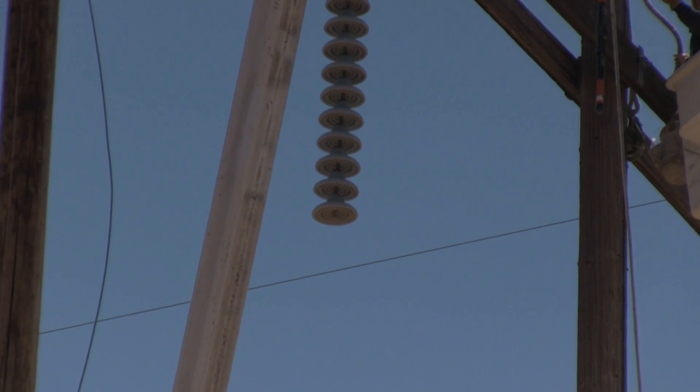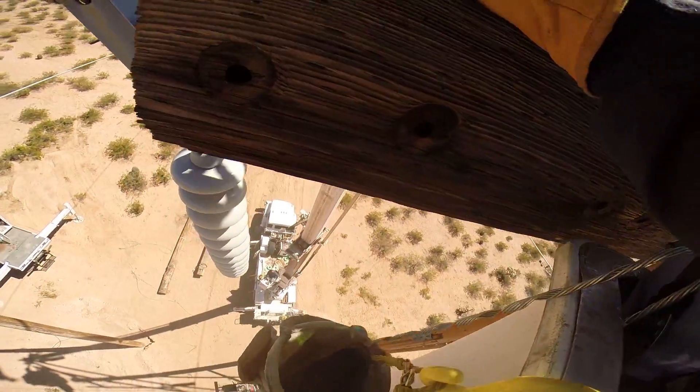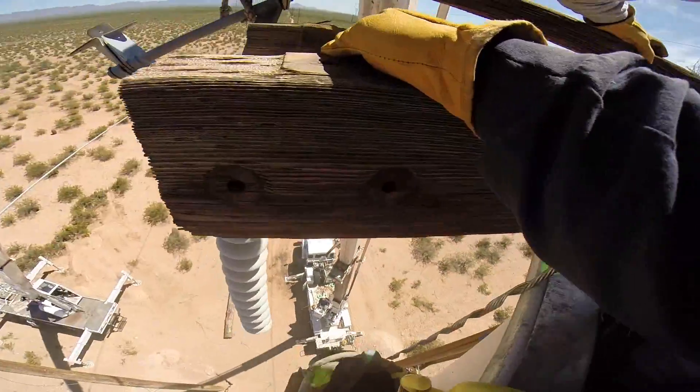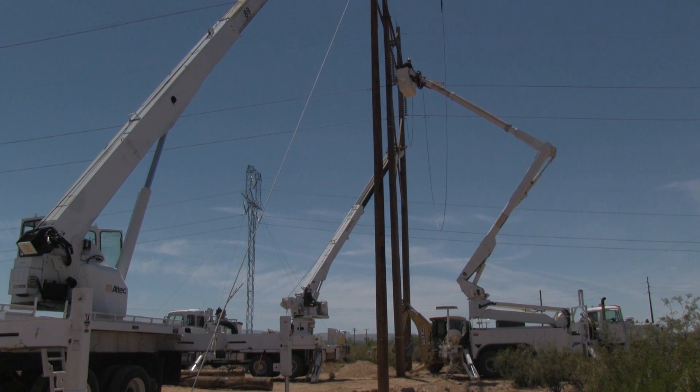On an energized line, you can go down to three or four people. Another way, which isn't seen here, is that poles can be replaced while the line is still hot or energized, which can be necessary when the grid has more demand or load. People need more power for air conditioning and other ways to beat the heat. In the summer, you can't de-energize that because we've got to feed this load — because of ACs and all the power in the summertime.